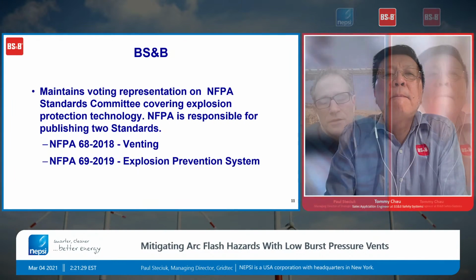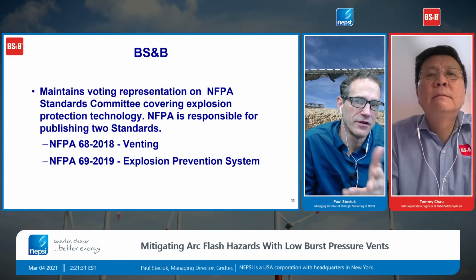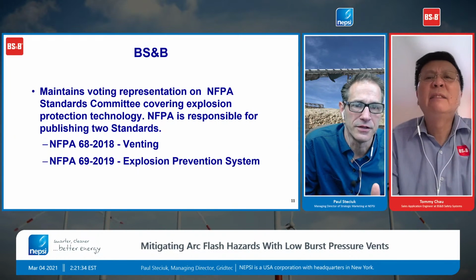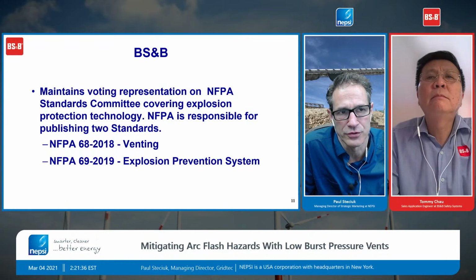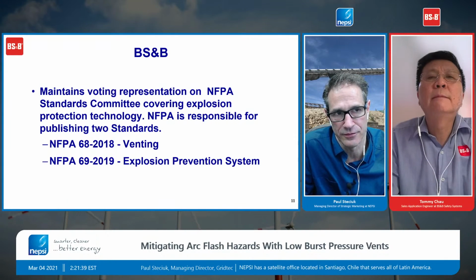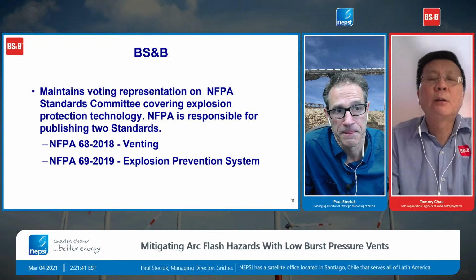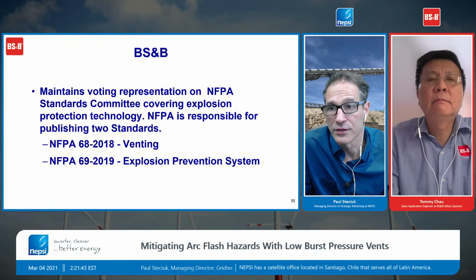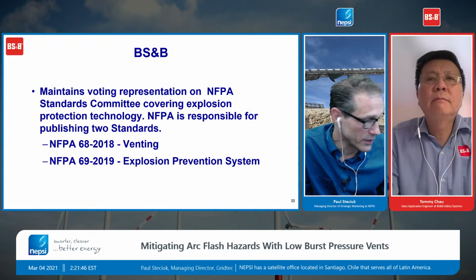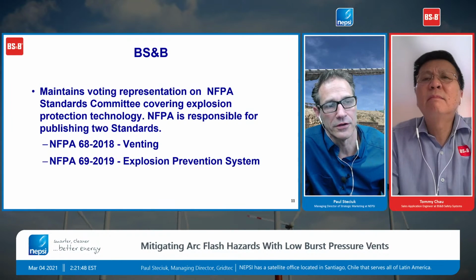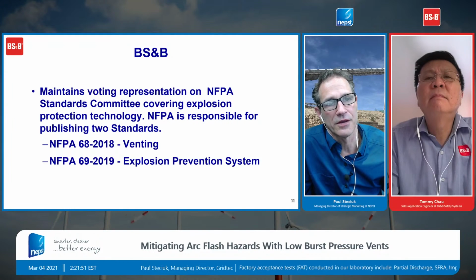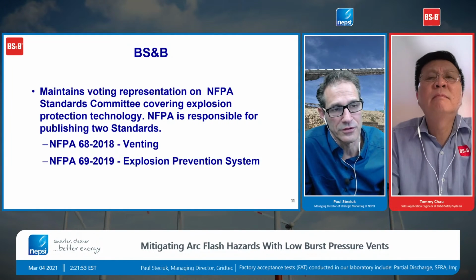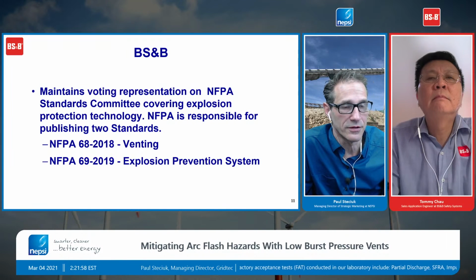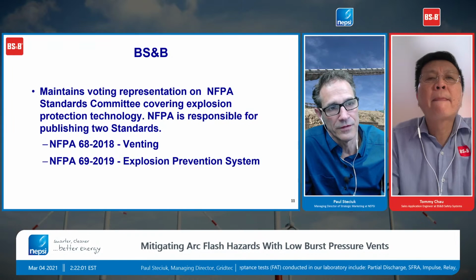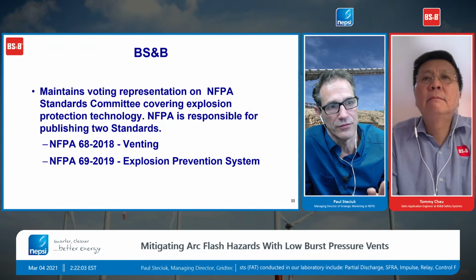So I think it's worth mentioning to the audience that NFPA 68 and 69 all have to do with explosions related to dust and not to internal arcs. Correct. So the audience should realize that what we are using here, these vents, really are intended for dust explosions. NEPSI decided that it makes sense to use these for the arc flash events also. And one of the reasons we like them is that we are able to seal off the internals of our equipment from the dust, from the environment.